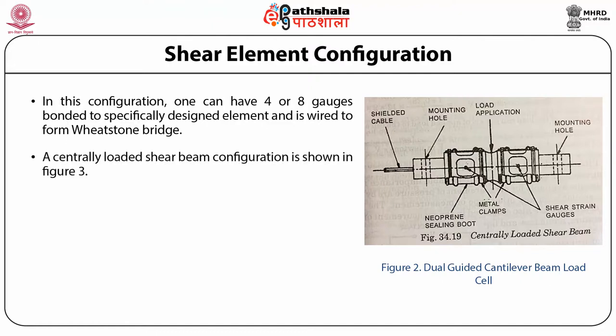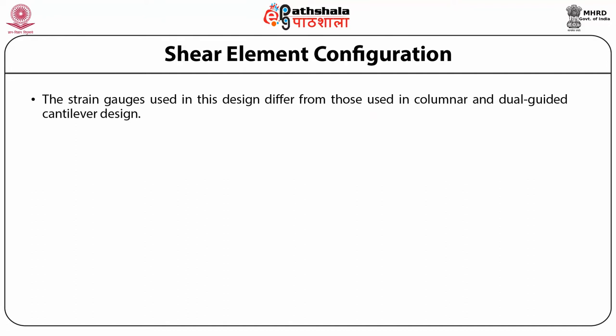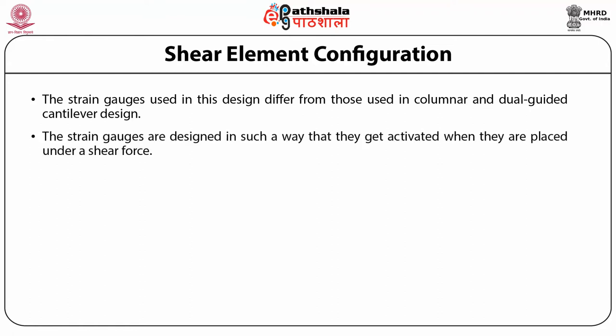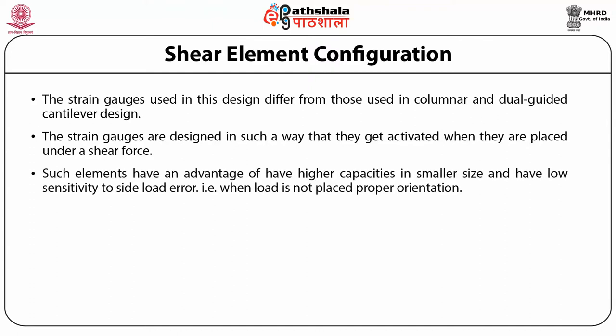A centrally loaded shear beam configuration is shown in Figure 3. The strain gauges used in this design differ from those used in columnar and dual guided cantilever designs. The strain gauges are designed so that they get activated when placed under a shear force. Such elements have an advantage of having higher capacities in smaller size and have low sensitivity to side load error, that is when load is not placed in proper orientation.